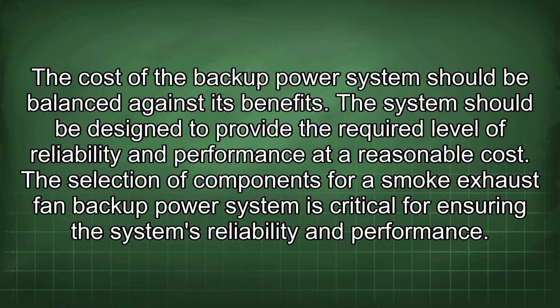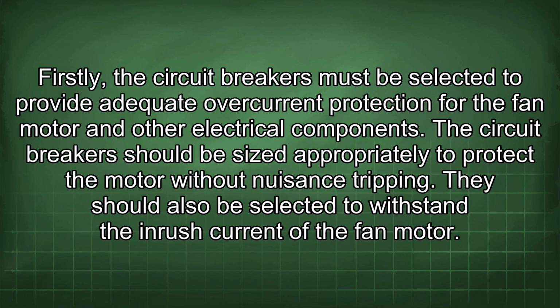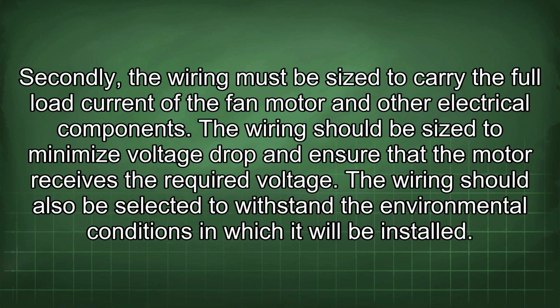The selection of components for a smoke exhaust fan backup power system is critical for ensuring the system's reliability and performance. Firstly, the circuit breakers must be selected to provide adequate overcurrent protection for the fan motor and other electrical components. The circuit breakers should be sized appropriately to protect the motor without nuisance tripping. They should also be selected to withstand the inrush current of the fan motor. Secondly, the wiring must be sized to carry the full load current of the fan motor and other electrical components.